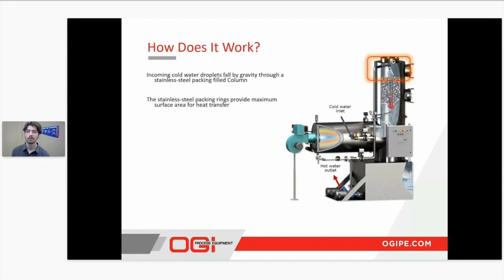So how does QuikWater work? As I mentioned, our incoming cold water droplets are going to fall through our spray nozzle at the very top of the QuikWater. That's going to make sure that you have that full conical spray passing down through your packing. As it is approaching that packing, it's going to be expanding the area for the heat transfer media. So you're going to see 99% of our heat transfer being captured in this small section here with this stainless steel packing. Essentially, with that area, you're going to be capturing as much heat as possible.